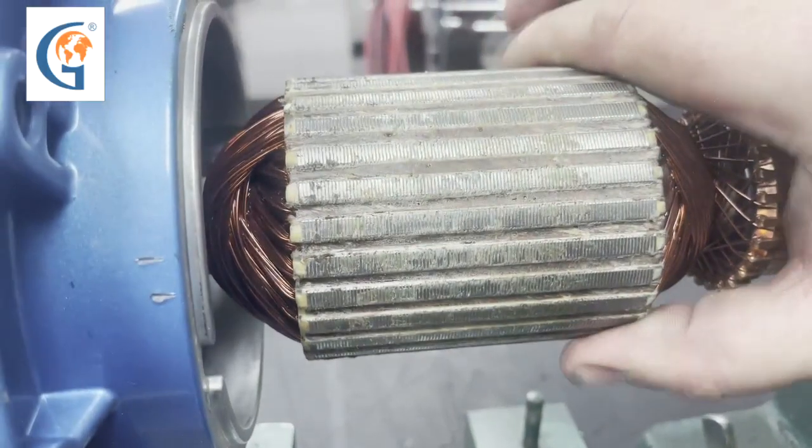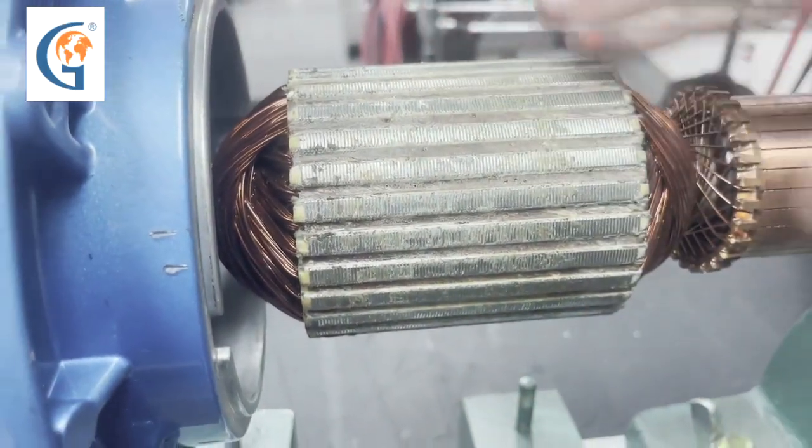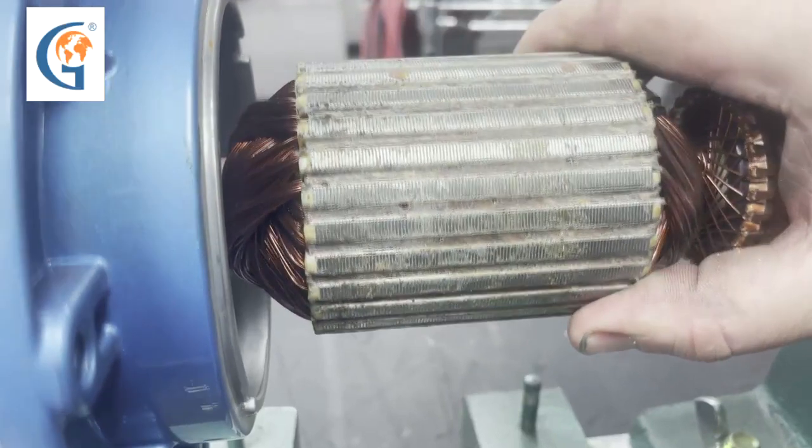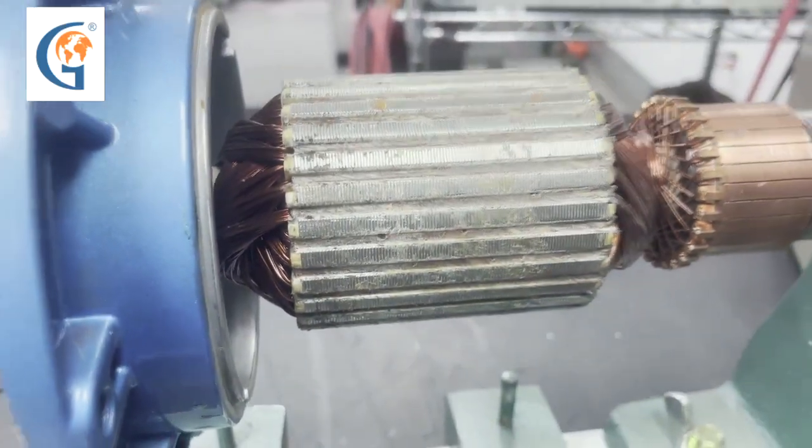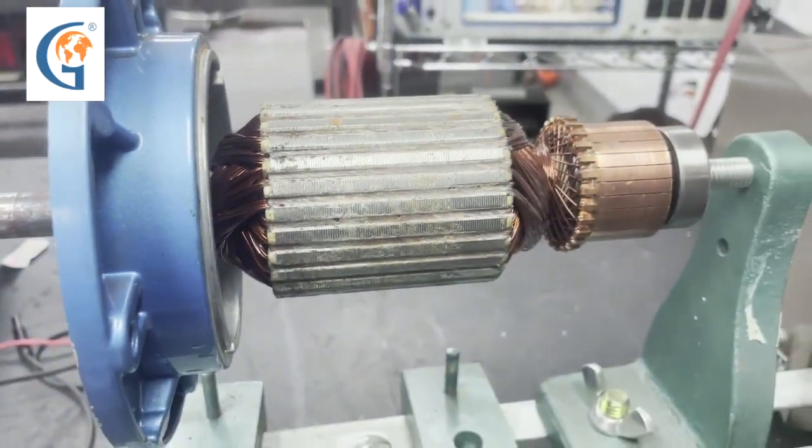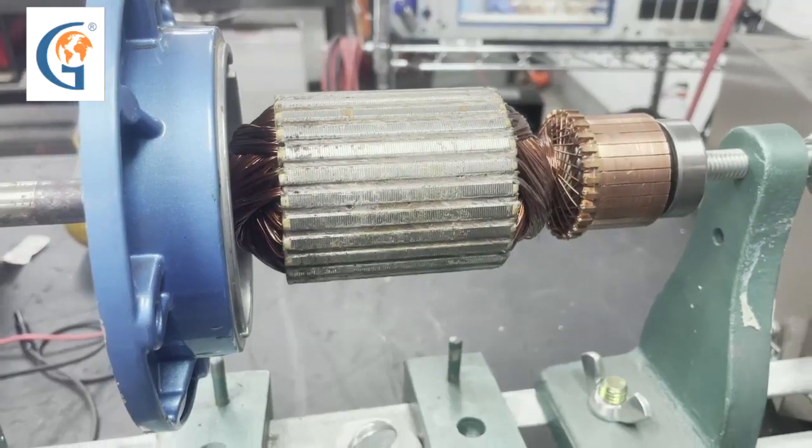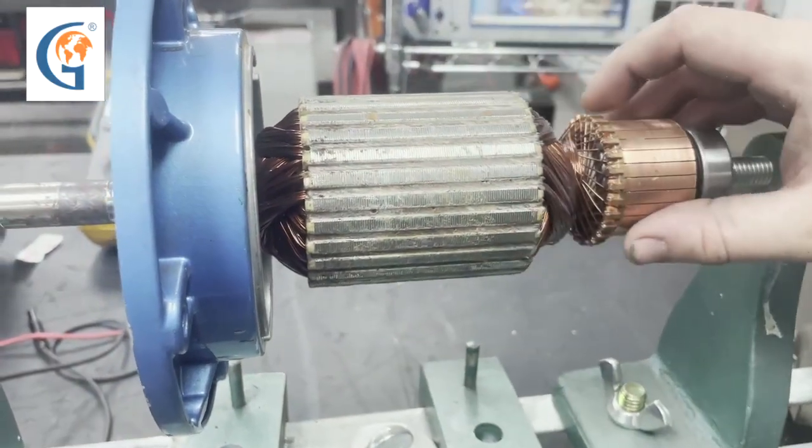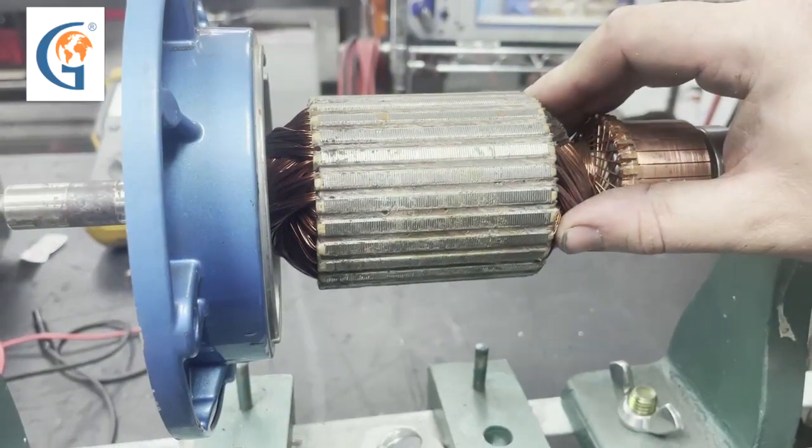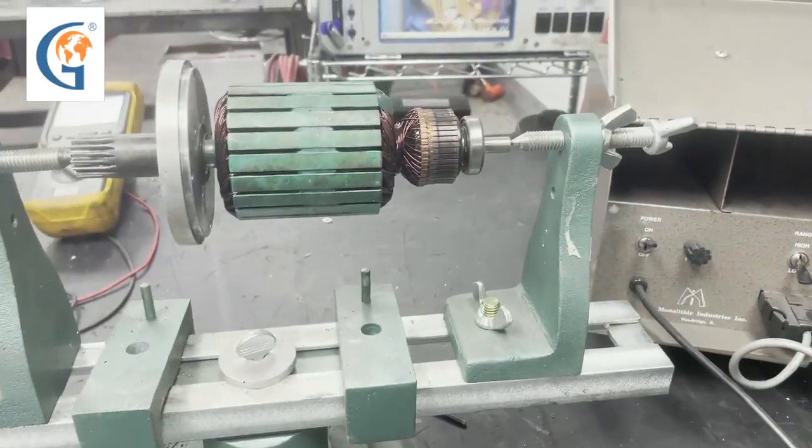We would need to get rid of that by washing and baking out this armature. That will get rid of some of the hopefully erroneous readings that we had. But this looks like an altogether good commutator and winding within this motor.